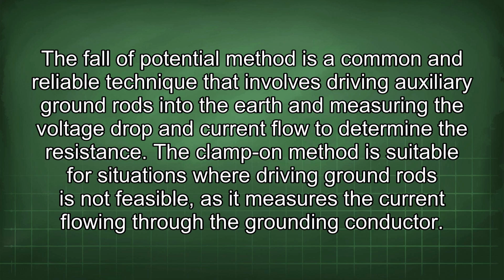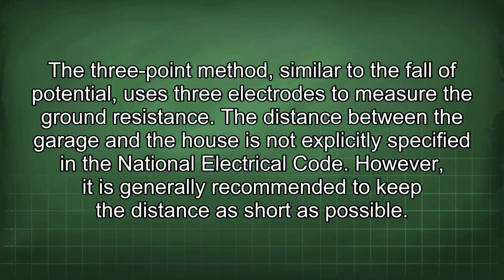The fall of potential method is a common and reliable technique that involves driving auxiliary ground rods into the earth and measuring the voltage drop and current flow to determine the resistance. The clamp-on method is suitable for situations where driving ground rods is not feasible, as it measures the current flowing through the grounding conductor. The 3-point method, similar to the fall of potential, uses 3 electrodes to measure the ground resistance.